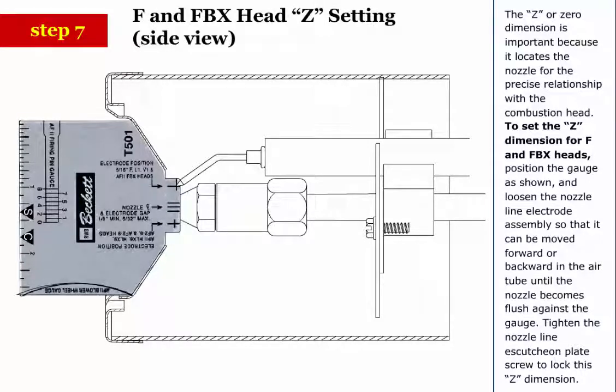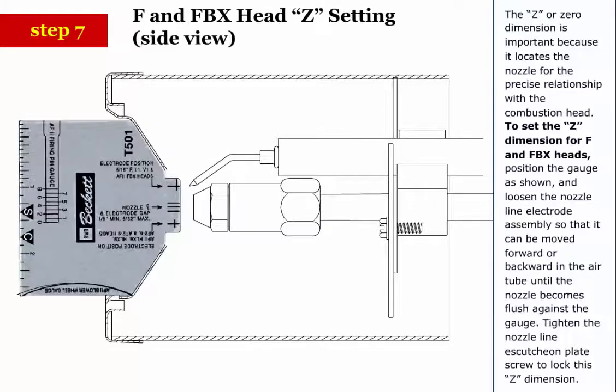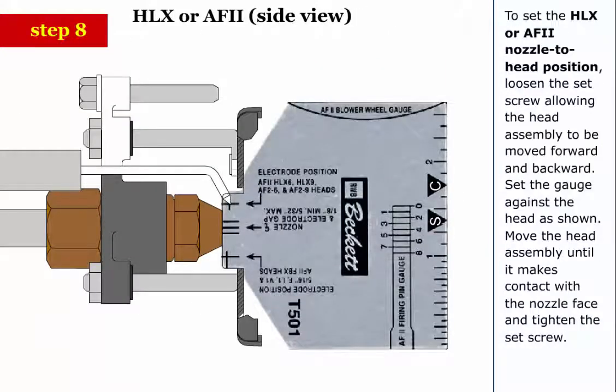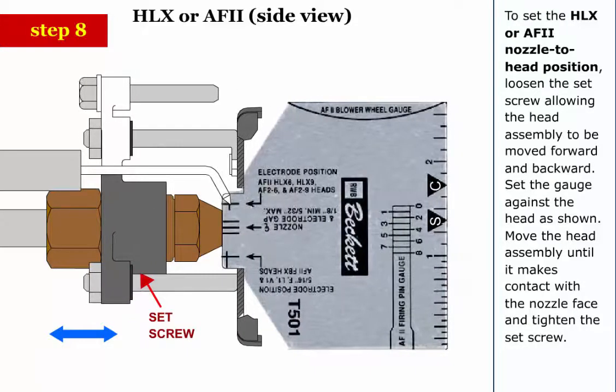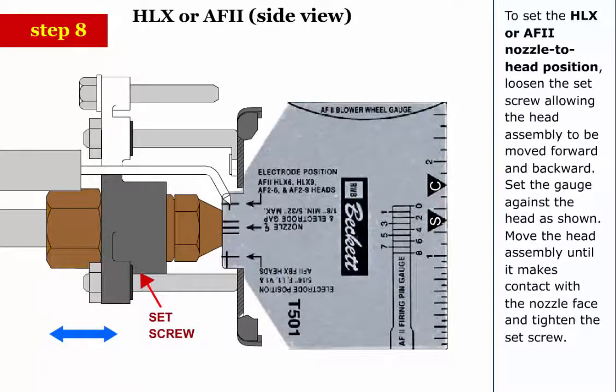Step 7: To set the Z dimension for F and FBX heads, position the gauge as shown and loosen the nozzle line electrode assembly so that it can be moved forward or backward in the air tube until the nozzle becomes flush against the gauge. Tighten the nozzle line escutcheon plate screw to lock this Z dimension. To set the HLX or AF2 nozzle to head position, loosen the set screw, allowing the head assembly to be moved forward and backward. Set the gauge against the head as shown. Move the head assembly until it makes contact with the nozzle face and tighten the set screw.